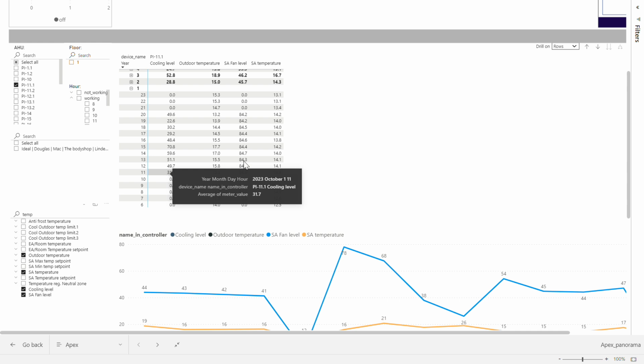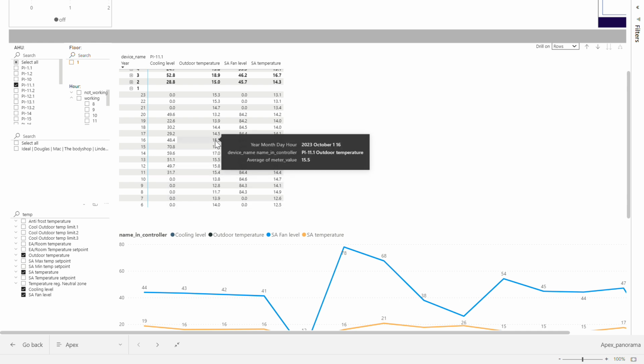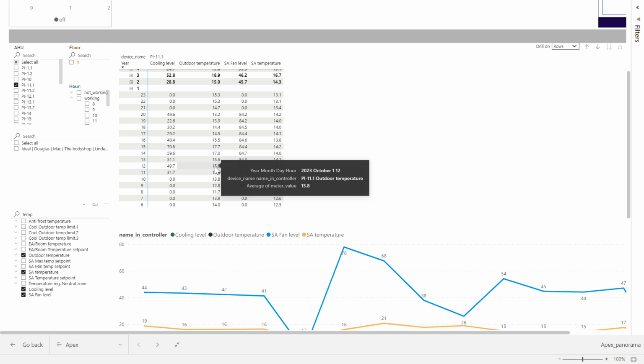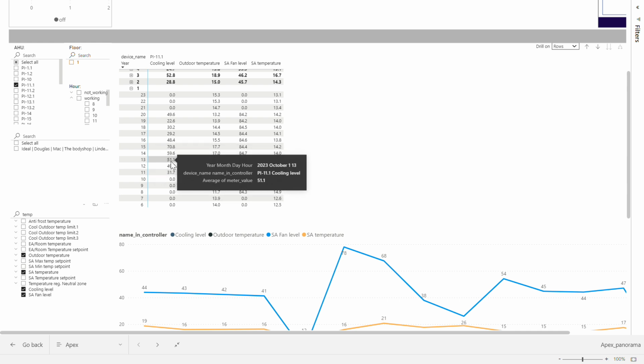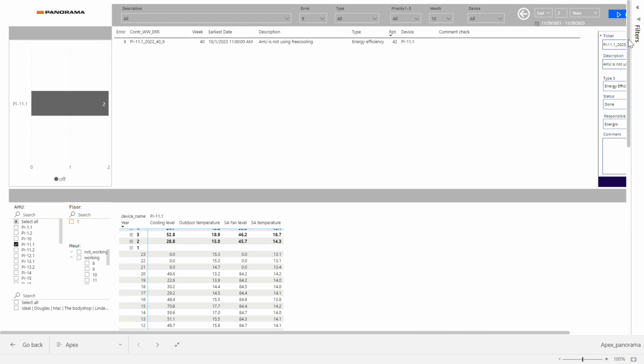So you probably understand that if outside air is like 14, 17 and so on, and my valve is open, I'm not using free cooling - outside is 14 and cooling is operating. This is an example where for an engineer to catch this, you'd have to scroll through a lot of Excel. So our platform indicates that directly.